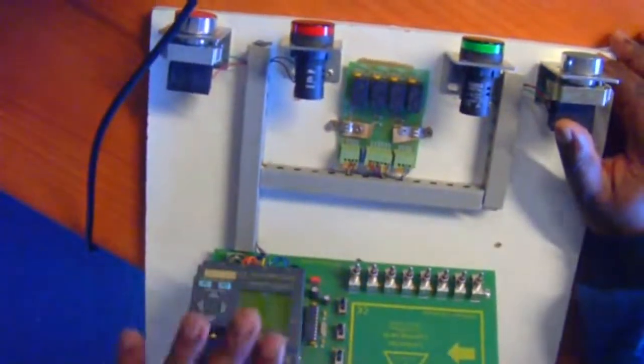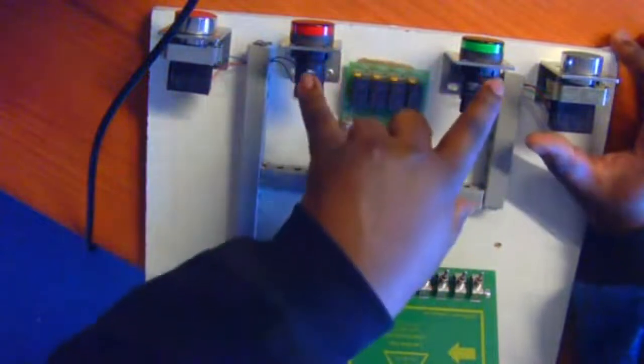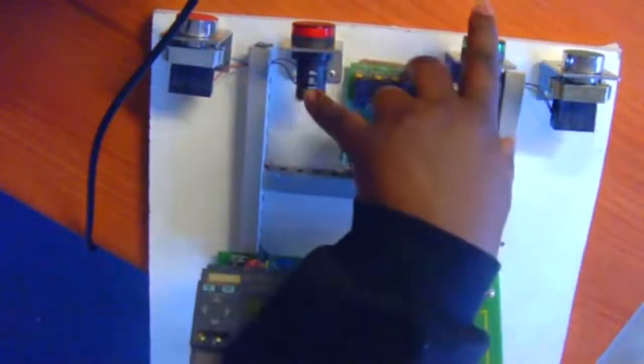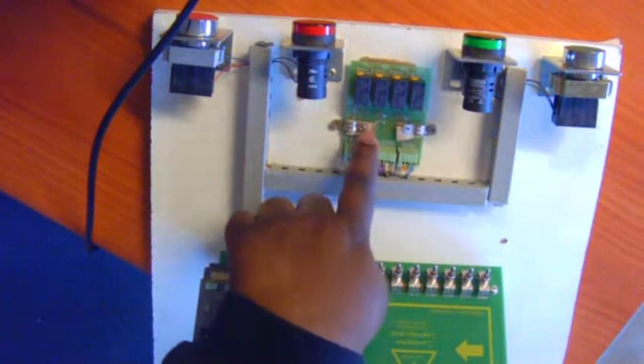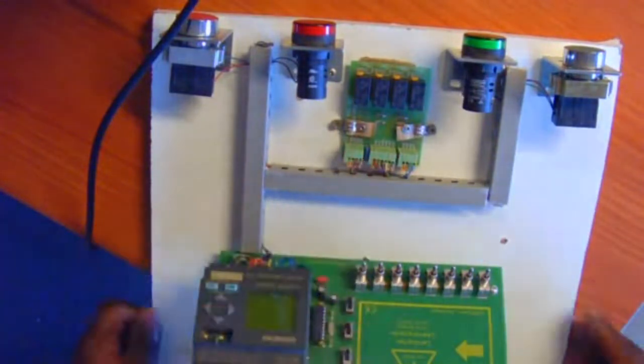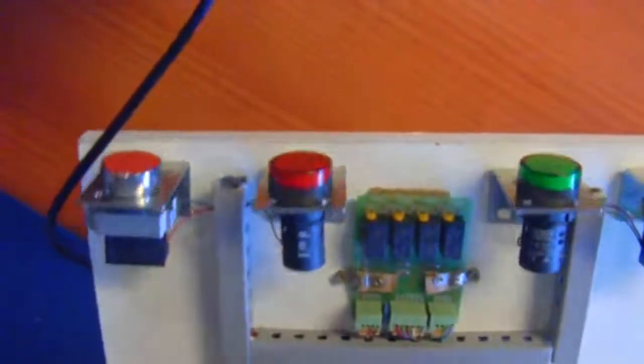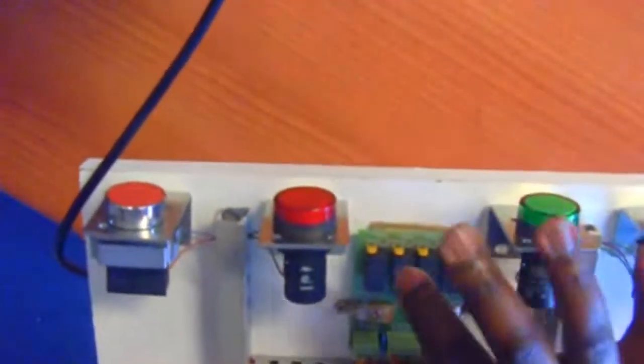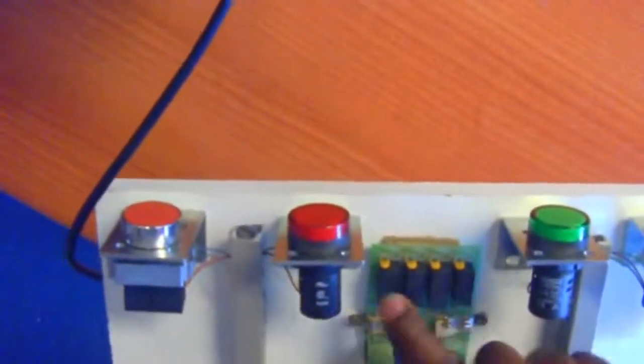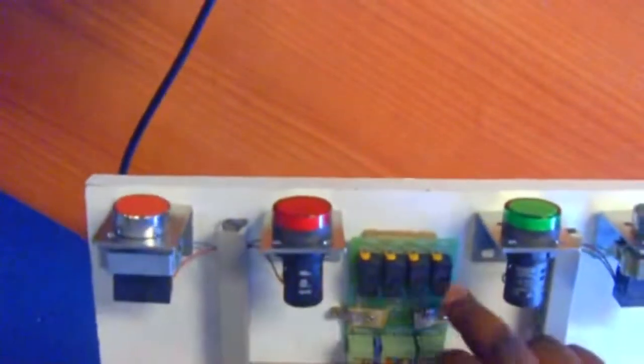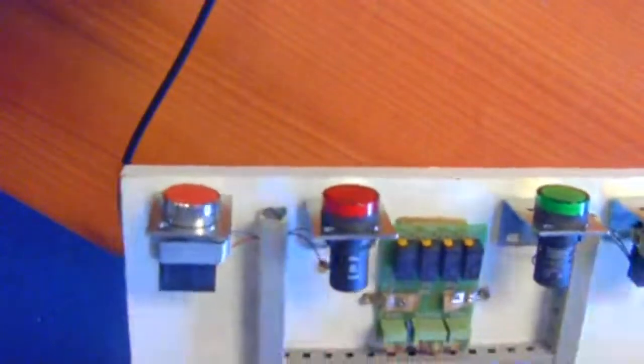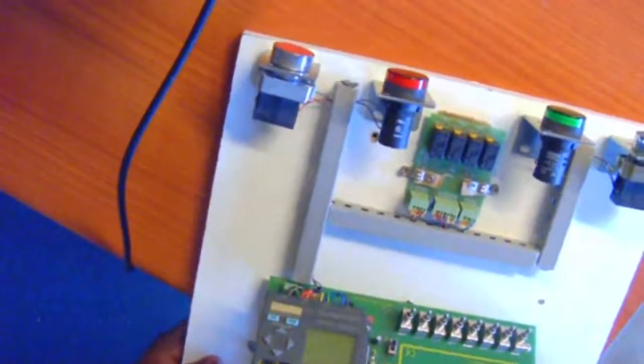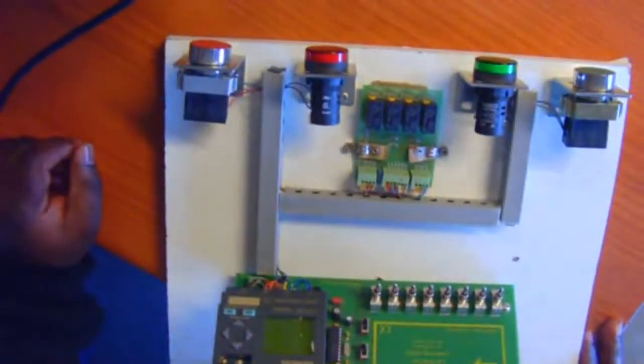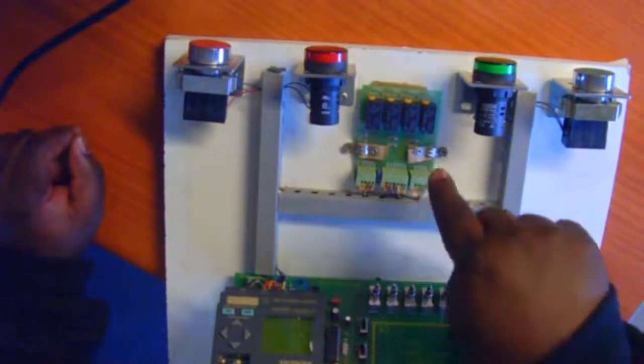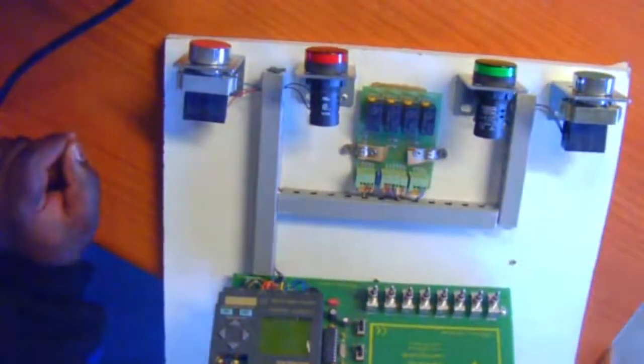But the signal from the PLC cannot power even mere 24 volt indicator lights. It cannot. It's not enough. So then you need a relay. Bring it closer so that you can see. So you need the relay. This relay is customized to suit four items, so it can control four devices. One relay can control four devices. Now, if I needed to push something of 240 volt, I will need a relay of 240 volt and connect it to the power source.